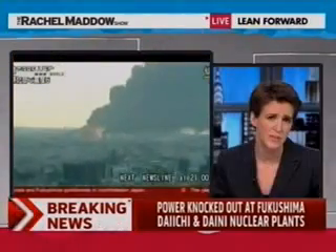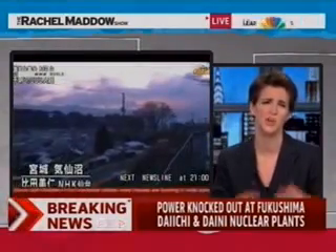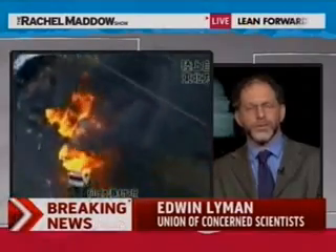When the authorities have put out statements today about pressure in some of these reactors rising — we saw one report that pressure in one of the Daiichi reactors was more than twice its designed capacity — what does that mean? The danger is that as the reactor gets hotter and the containment atmosphere gets hotter, the pressure will increase. And in order to avoid a potentially catastrophic rupture, you release some of the pressure by venting some radioactive gas now and avoid a larger catastrophe later. So it's really a devil's bargain — the radiation exposure from moderate venting is going to be a lot less than if this accident actually progresses to a worst case, where we have a full-scale core melt and then a catastrophic rupture of the containment.